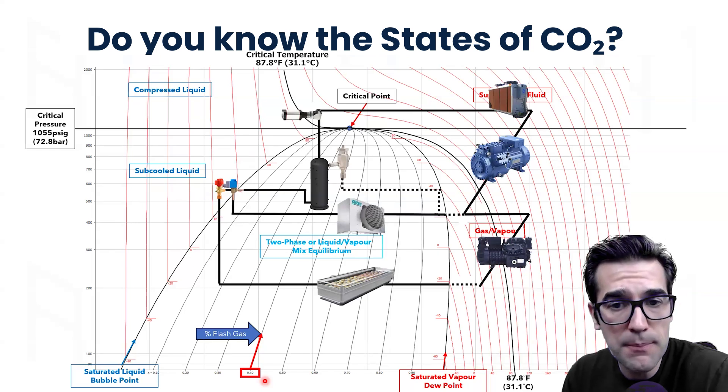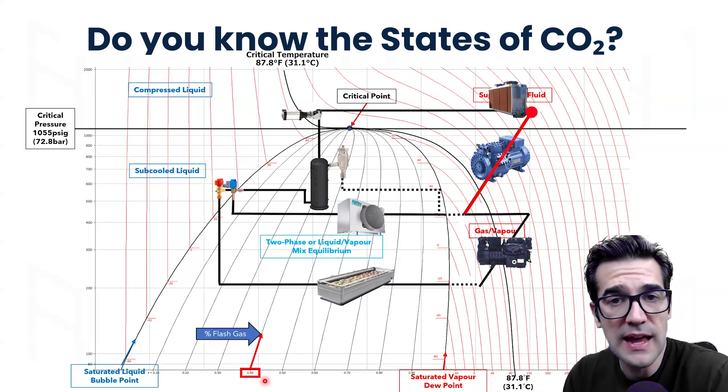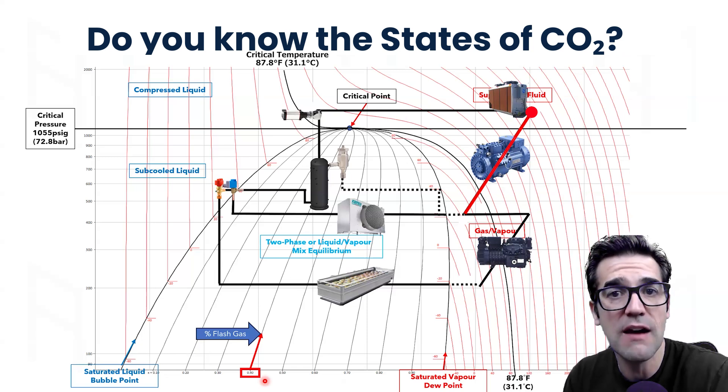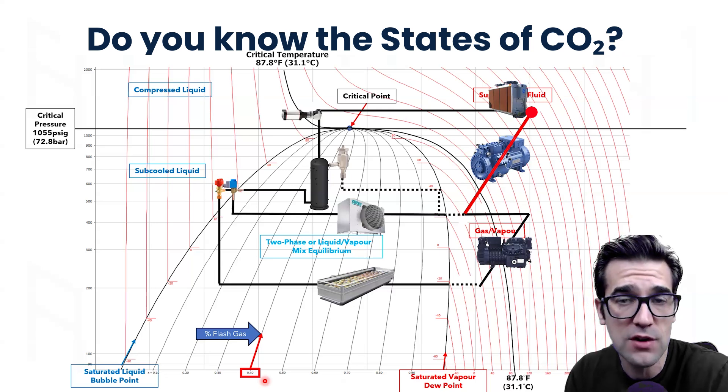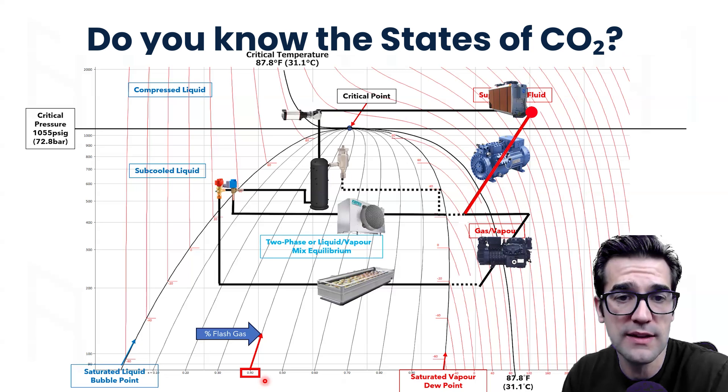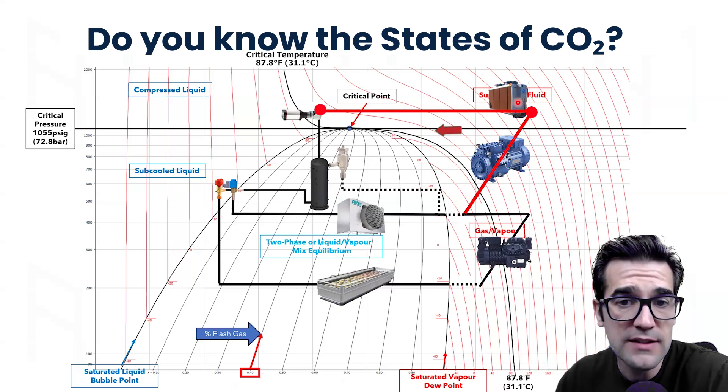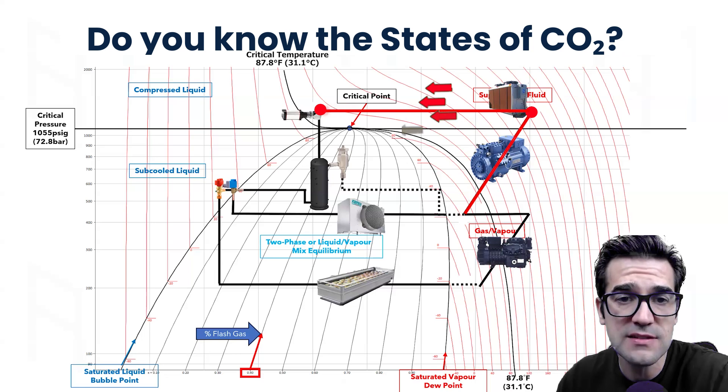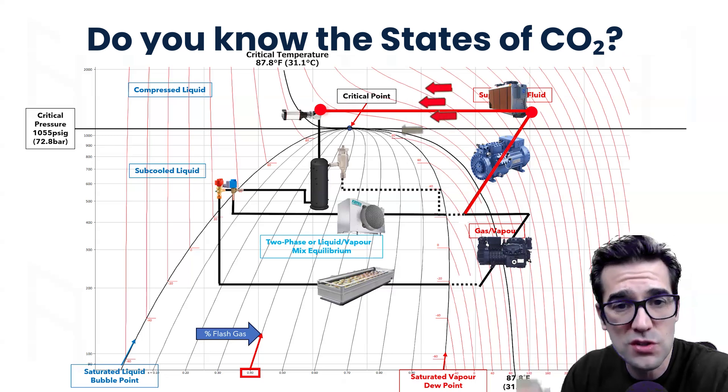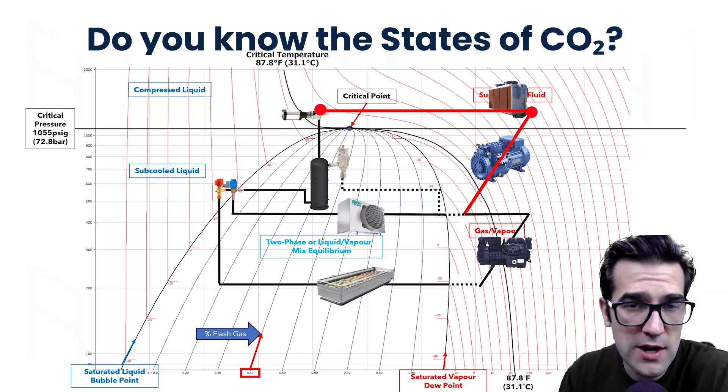How that medium temp compressor is running in this application. When it compresses that vapor, that gas vapor CO2, a supercritical fluid is leaving that compressor, traveling down the discharge line to the gas cooler condenser. As it travels through the gas cooler condenser, a supercritical fluid comes to this high pressure valve because we're still above the critical temperature and the critical pressure.